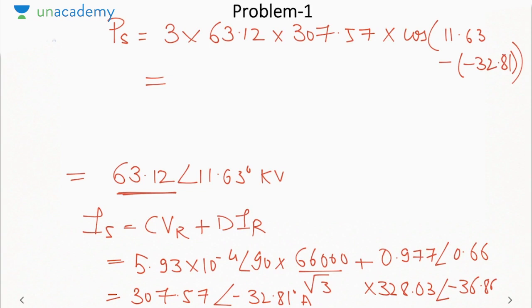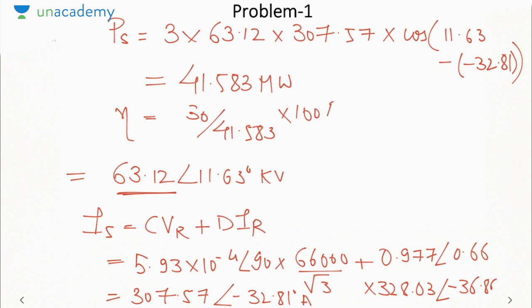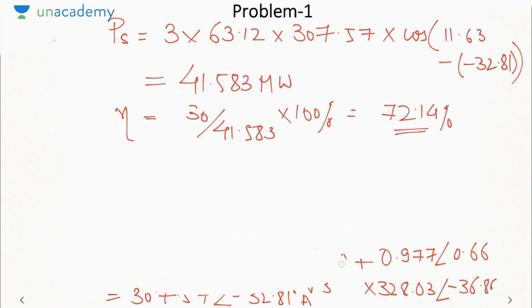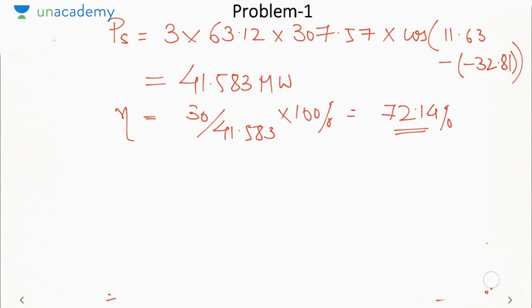So this comes out to be 41.583 megawatt. Now efficiency will be output by input, that is 30 by 41.583 into 100%, that is 72.14%, which is quite low due to high resistance. Otherwise, in transmission lines, the resistance is much less than reactance. Here it is comparable. So due to high resistance, the efficiency is low.